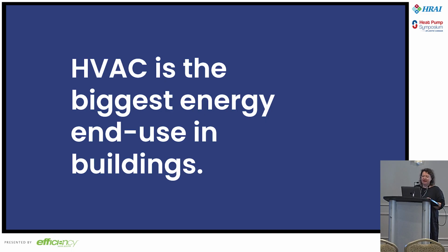Zooming in on HVAC, heating and cooling accounts for at least 60% of the energy used by most of our buildings, at least in our region. And if we improve the building envelope by adding insulation, sealing air leaks, and replacing windows, the heating and cooling loads can drop by up to 75%. That changes the size and the distribution approach, and also significantly, depending on the system, the cost.